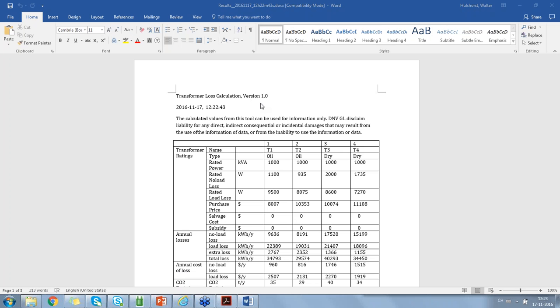And there you will see a standardized report, which you may adapt as you want. In this case, it shows you the 4 transformers that we have selected and all the input data, and there you can see that, for instance, transformer 2 has a lower rated no load loss compared to the other transformers. You can also identify that transformer 4 has a lower load loss rating. The purchase price is mentioned over there.